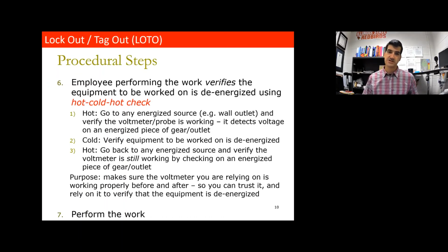This is the procedure for a hot, cold, hot check. It's not just that you take your voltage probes and stick them in there to check for voltage -- it's more than that, because we want to guarantee the multimeter or voltage probe is working properly. The big picture is making sure the equipment is de-energized, but to do that, I need to make sure my multimeter is working properly when it tells me there's no voltage inside.